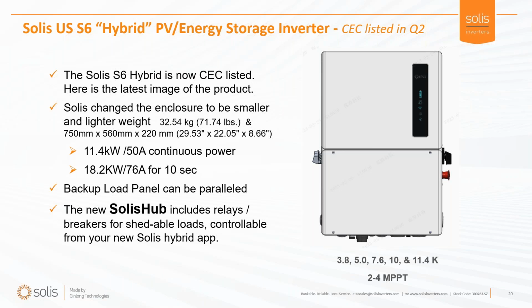But you don't need to do that. You can just tie in on the load side, like we always have, and then parallel the inverters. There's an RJ45 jack in these inverters, and you can parallel them with Cat5 cable, CAN bus type connection, and stack your backup breakers into a small AC load panel and then into a backup panel. So this 11.4 inverter does 47.5 amps - times 2, you're into 95 amps continuous.